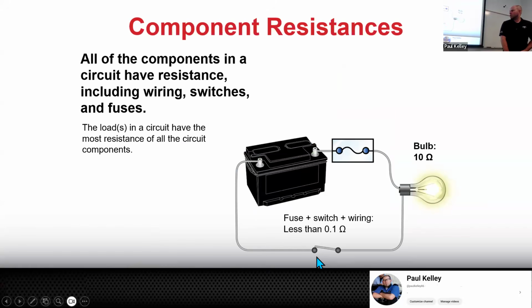What we might deal with, though, is like this switch. What do you think a failure of that switch could be? That switch has got contactors, right, like this - contactors. So what if there's corrosion on the contactor? Well, what if it's just a little bit of corrosion? It should be 0.1 ohms, or maybe even potentially like 0.2 or less.